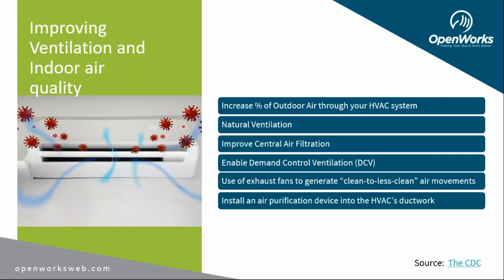Demand control ventilation can also eliminate other common strategies, such as running your HVAC system for 2 hours before an occupied period to clean the air, or opening fresh air dampers to a higher percentage than we're not necessarily sure that we need. While utilizing the CO2 sensor, we'll be monitoring the quality of the air in the building, and we'll only bring in fresh air when we need to in order to satisfy our air quality standards, or if it makes sense to do so from an energy saving standpoint. It's truly the best of both worlds.